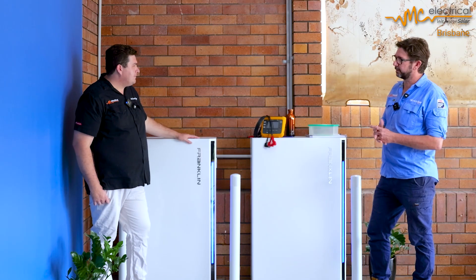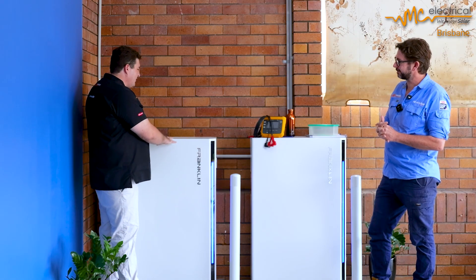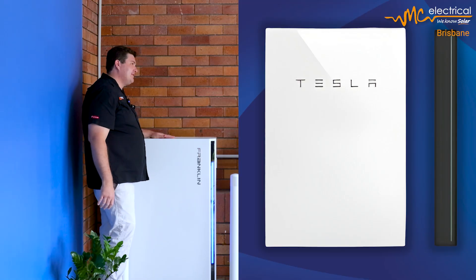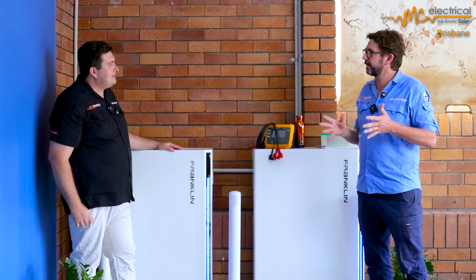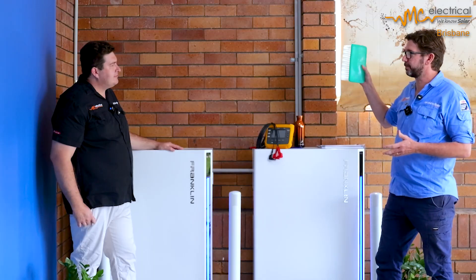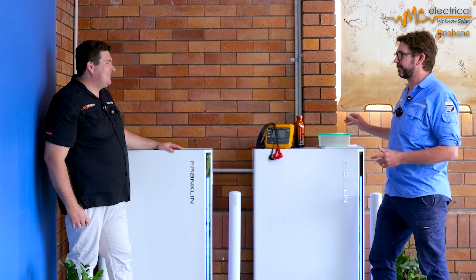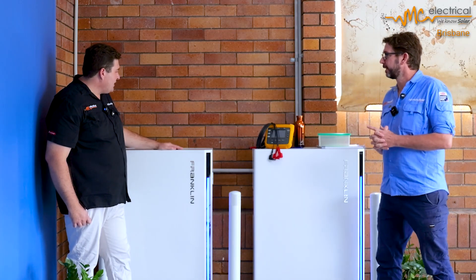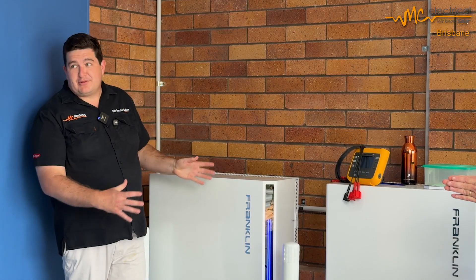In reality this is going to run not quite as efficient as Fronius, but I was actually super impressed. All my theory that usually works out — looking at these cells — the Franklin battery's design didn't try to cram everything in or put the inverter straight on top heating everything up. It actually ran relatively efficient compared to what I would have thought. These are huge batteries — I reckon I could fit two Powerwalls in the same footprint as one of these units. People are trying to make batteries as small as possible, but cramming in really big energy-dense prismatic cells together without worrying about heat isn't necessarily the smartest thing. If you want longevity, less energy-dense is quite often the better way to go.